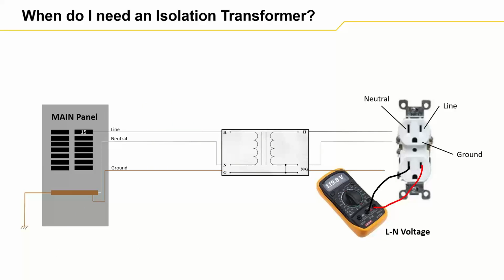So what can you do about it? One option would be to run a new larger gauge wire. This would reduce the wire resistance, and thus the voltage drop. However, running a new wire is often not feasible. It's already in the wall, and you can't get to it. Another option to solve this issue is to use this isolation transformer, and preferably you use it at the point of use, meaning at the rack location.